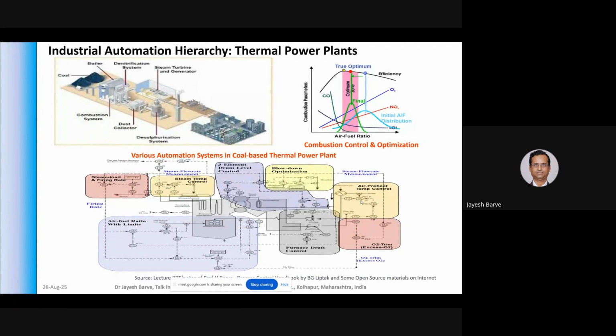When I do steam flow control, I should also ensure that steam temperature is enough, because if steam temperature goes low, steam will condense. I don't want steam to condense in the multiple stages of the steam turbine. So steam temperature has to be maintained.